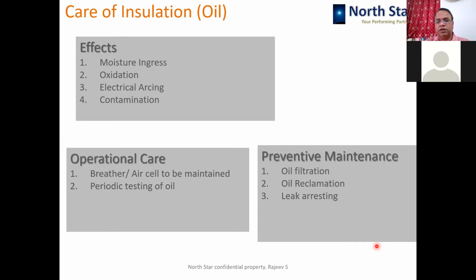How these leaks are causing the damage is when the transformer is under cooling period, when the load is less on the transformer, so negative pressure gets generated inside the transformer because of contraction of the oil. And in that situation, it breathes in. So primarily it breathes through the breather, but it also breathes if there are some leaks in the transformer, some gaskets have given away. And from there, the moisture also goes inside.